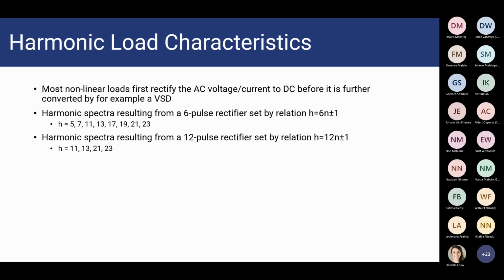All right, so just a few examples of characteristics from specific loads. A 6-pulse rectifier, for example, normally generates the 5th, 7th, 11th, 13th, 17th, 19th, 21st, and 23rd harmonic components. So here's the formula you can use: it's 6n plus or minus 1. So the first 2 harmonics you can expect are the 5th and 7th harmonic. And then similarly, you can use this formula to calculate what harmonics are normally generated by 12-pulse rectifiers. That's the 11th, 13th, 21st, and 23rd.